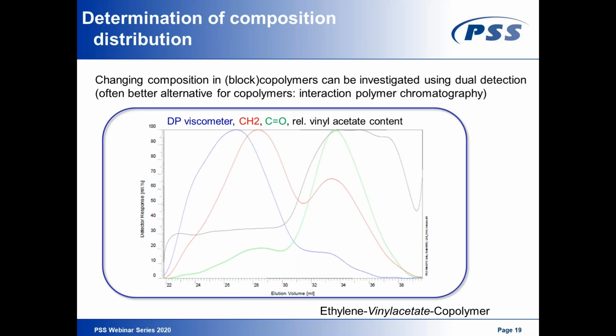As an example, I've picked a very nice example from high temperature GPC SEC. I think most of you are aware that polyolefins cannot be measured in ambient GPC SEC because polyolefins do not dissolve at low temperatures. You have to use very specific solvents at very high temperature to keep them in solution and to enable GPC SEC separation. On the upside, there's also an advantage, because the solvents you are using allow IR detection, something which is not possible in ambient solvents like THF or chloroform or toluene. So when you're using high temperature GPC and you have, for example, an ethylene vinyl acetate copolymer, you can monitor the change in composition by comparing the two detector signals.